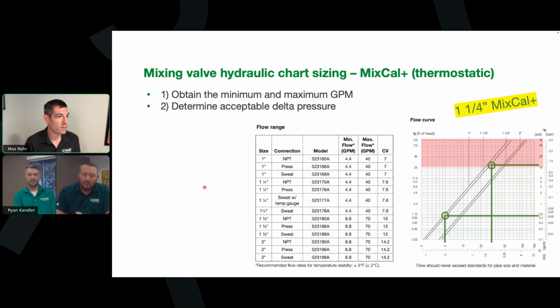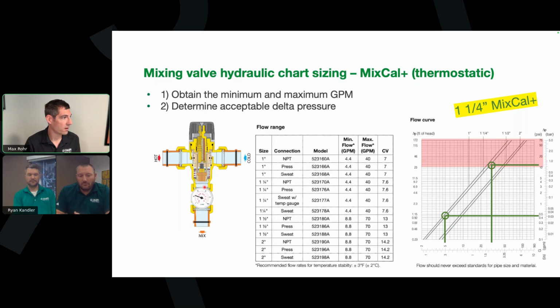Now, if you haven't ever seen a cross section of the thermostatic mixing valve, this is pretty common to get, like an ASSE 1017 listing. You're going to have a pretty similar shape here. There's not miles in between the different manufacturers of how you make a thermostatic mixing valve. It's kind of more in the materials and the consistency and the machining and things like that. This has a C sub V of 7.6.